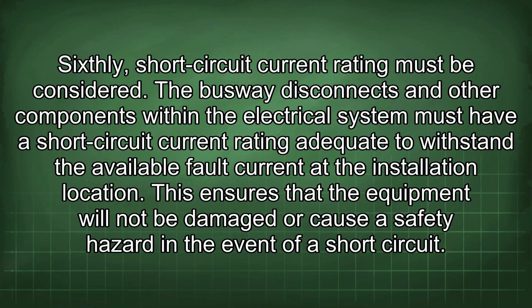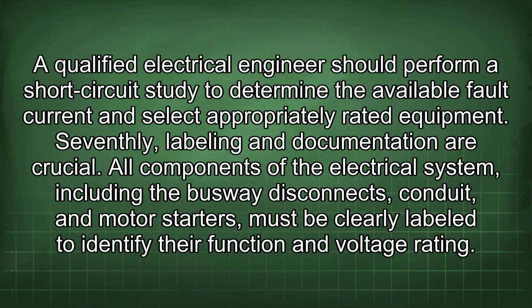Sixthly, short-circuit current rating must be considered. The busway disconnects and other components within the electrical system must have a short-circuit current rating adequate to withstand the available fault current at the installation location. This ensures that the equipment will not be damaged or cause a safety hazard in the event of a short circuit. A qualified electrical engineer should perform a short-circuit study to determine the available fault current and select appropriately rated equipment.